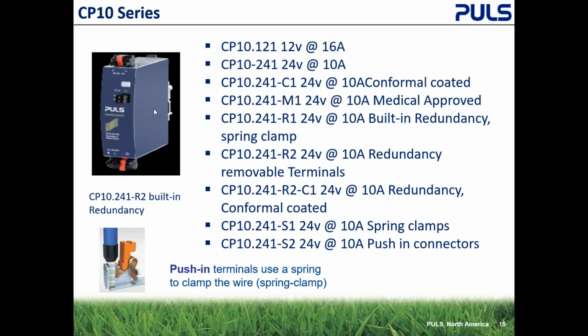So if you have a power supply go down, you'll have two of these. You don't need a redundancy module. Two of these wired in parallel to the load. If one power supply drops out, the other power supply takes over. And it doesn't backfeed because the redundancy is built into the power supply.